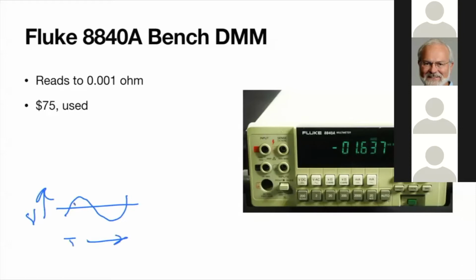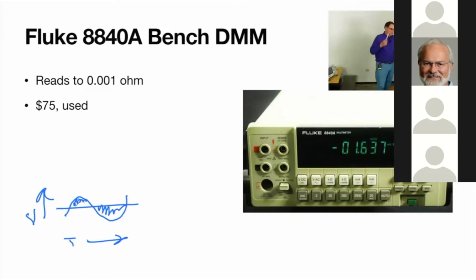We essentially are measuring the voltage under that curve, and we have to do a mathematical operation on it to do that. It's actually doing calculations in real time. Yeah, exactly. So a non-RMS meter will take an average in there. And I'm not actually sure how they do that, if they integrate that with a capacitor or something like that.